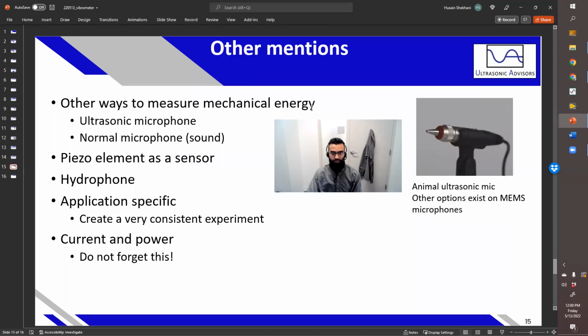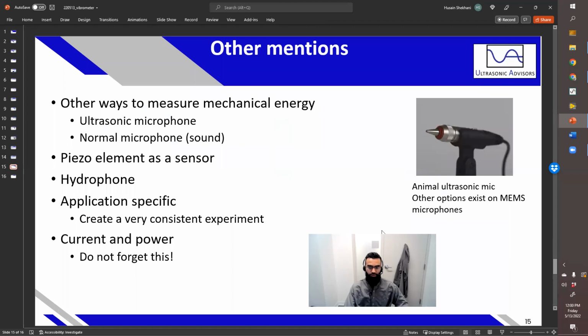Here are other mentions. There's not just vibrometry to measure oscillation. There are other ways to measure mechanical energy. One interesting point, I haven't been able to use this myself, but I am meaning to do it at some point, is to use an ultrasonic microphone. All the transducers that oscillate at ultrasonic frequency are emitting sound waves. So assuming you have all your holding and placement constant, you would be able to use an ultrasonic microphone to measure the pressure coming off of the transducer, assuming you have a very consistent standoff distance, and there are probably a couple of other things you need to consider. But it is an option that you can use.